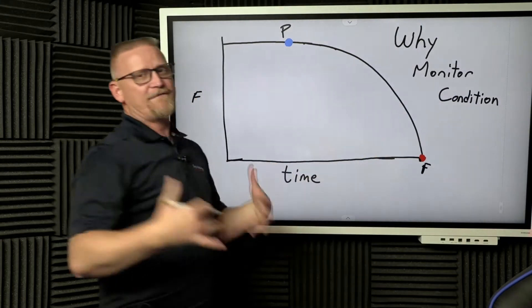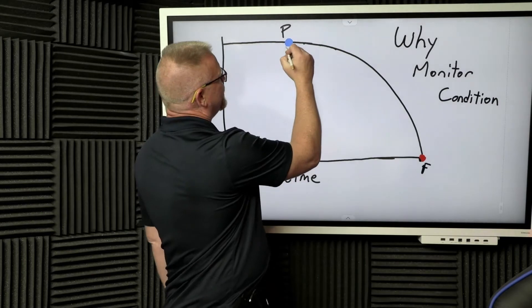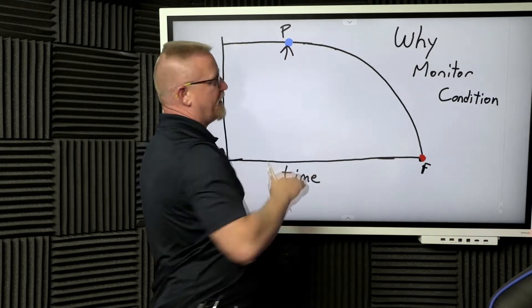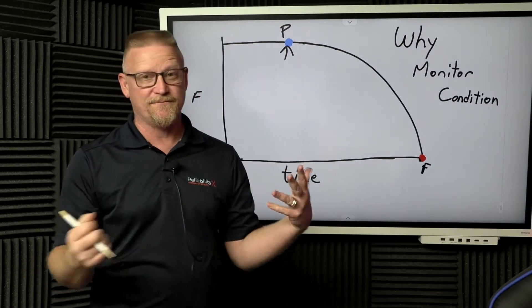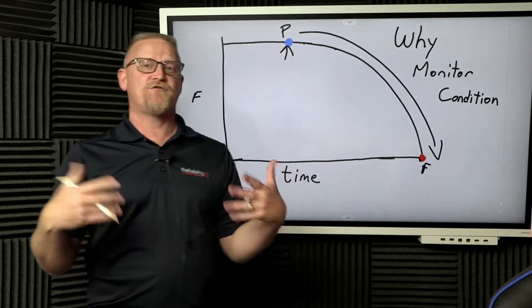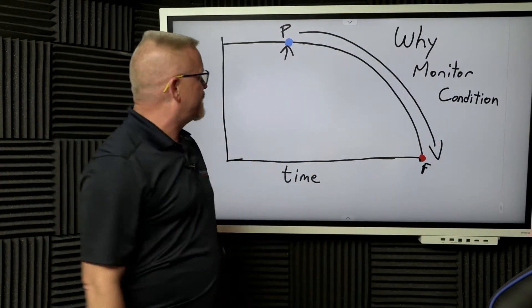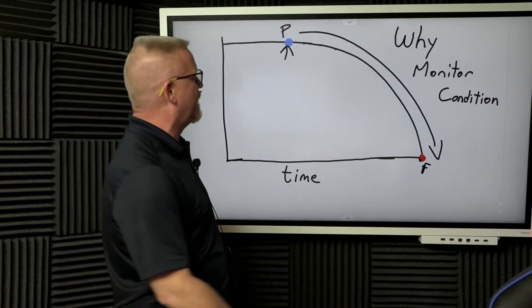This is our PF interval or PF curve. It is the point in time from when a potential catastrophic event is going to occur, meaning I put some dirt in my bearing, all the way until such time that the catastrophic event happens where I blow apart the bearing, drop my shaft on a pillow block, score the pillow block, and destroy a bunch of equipment.